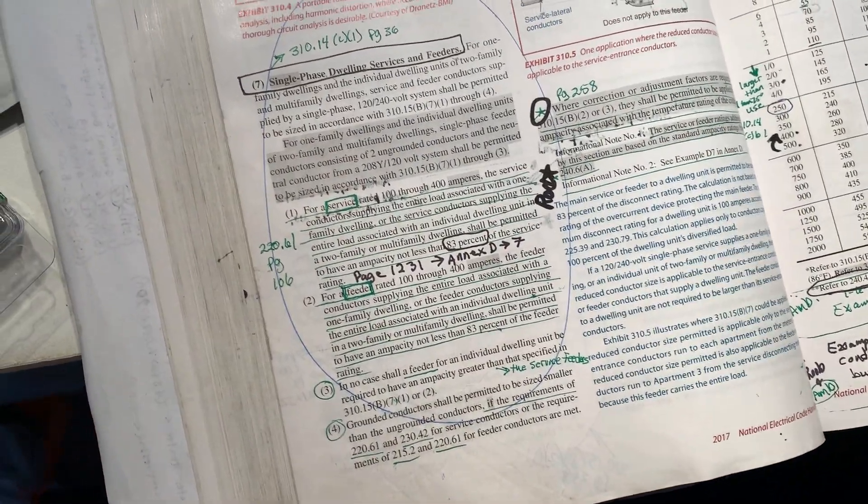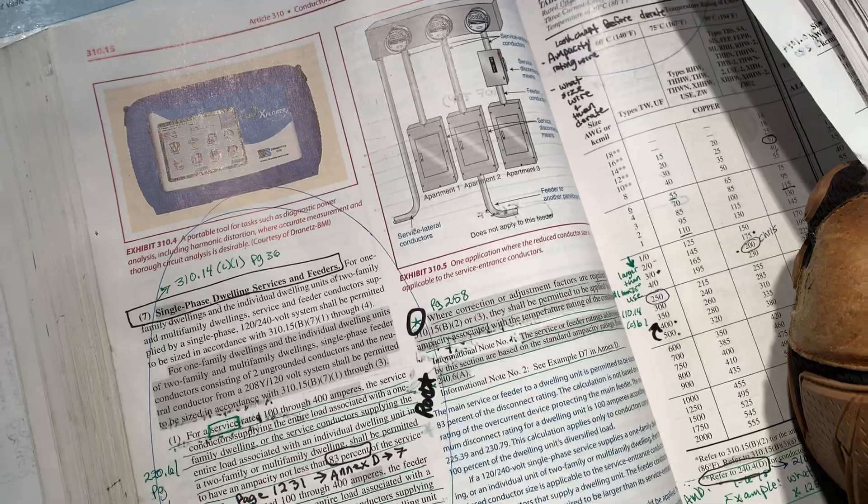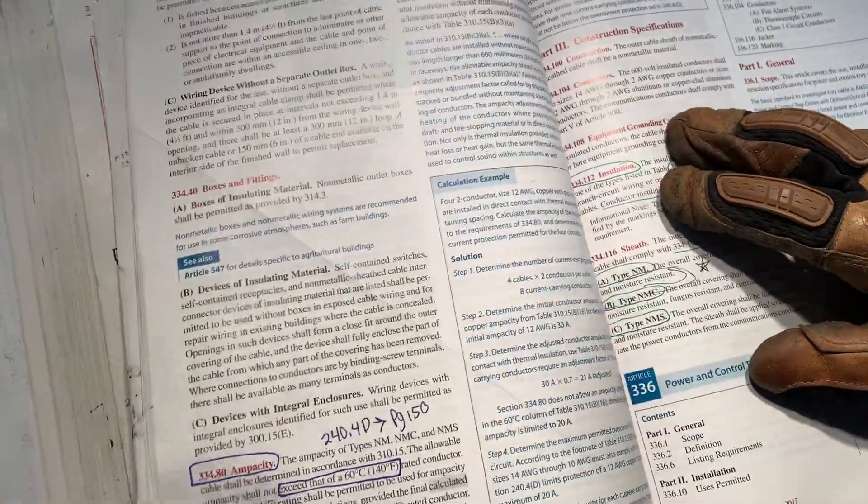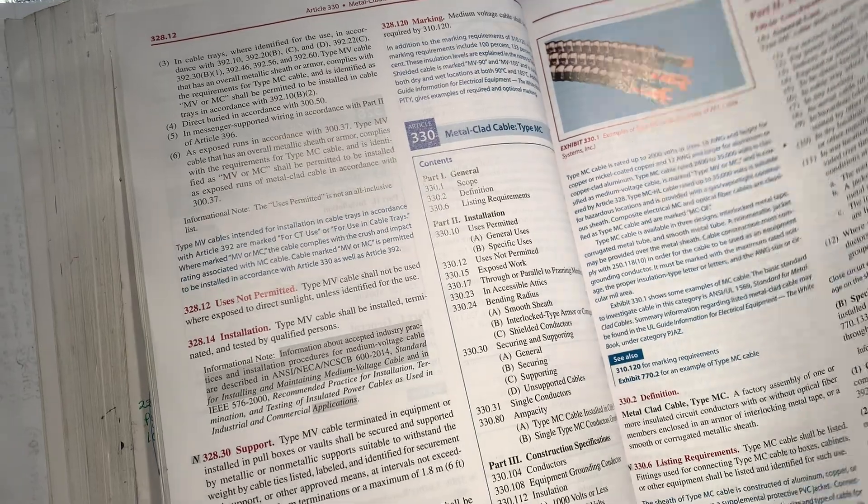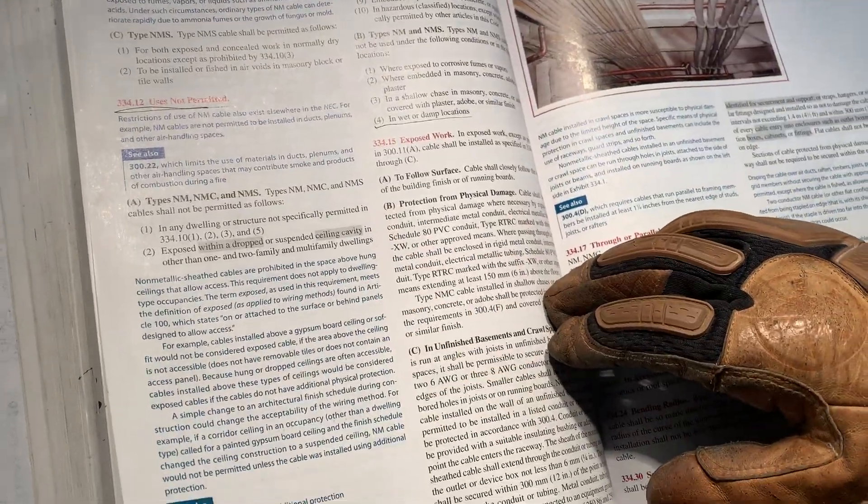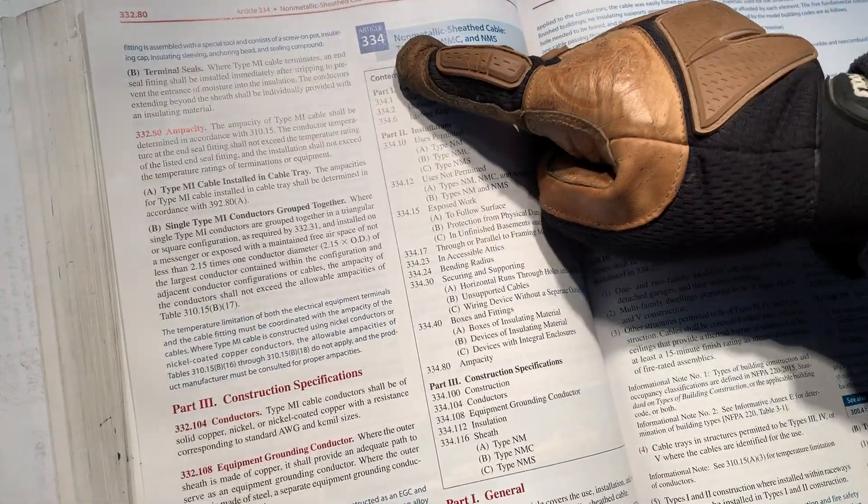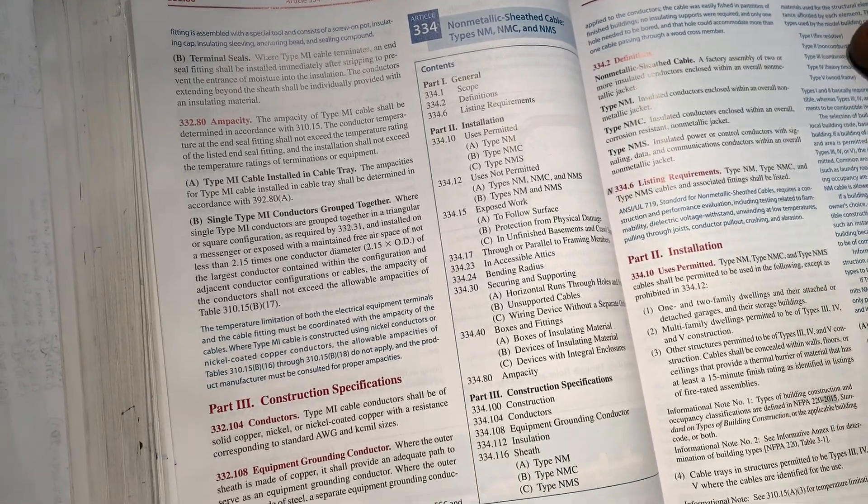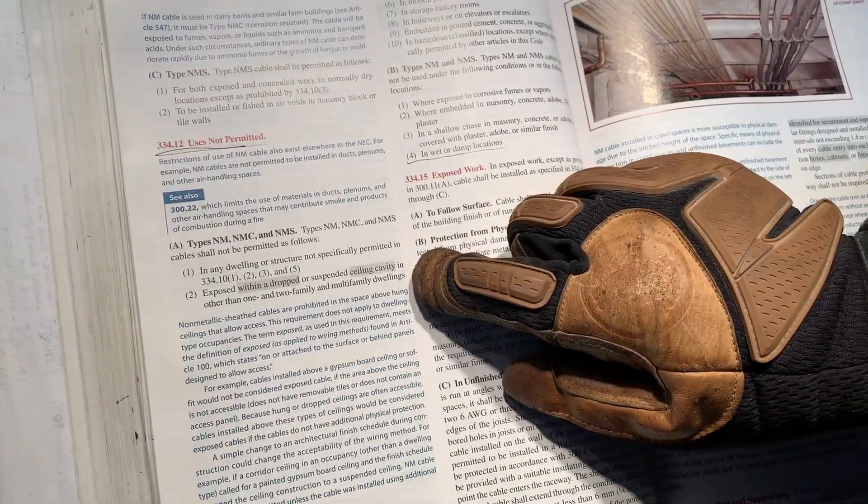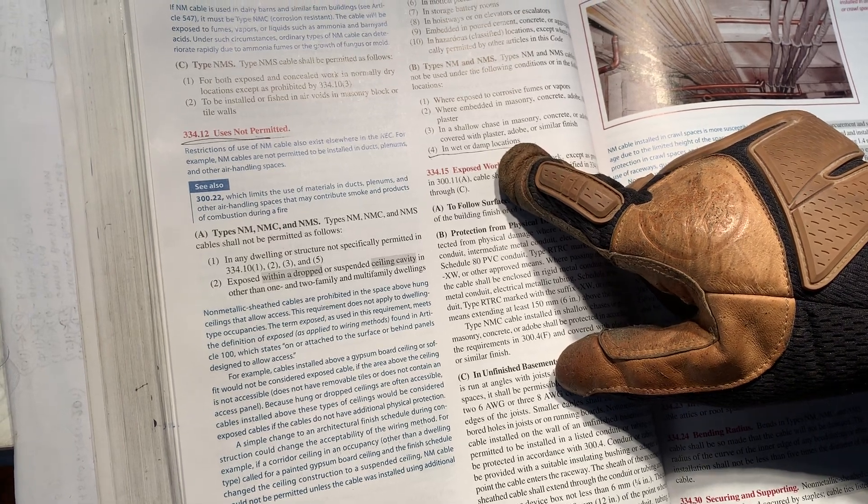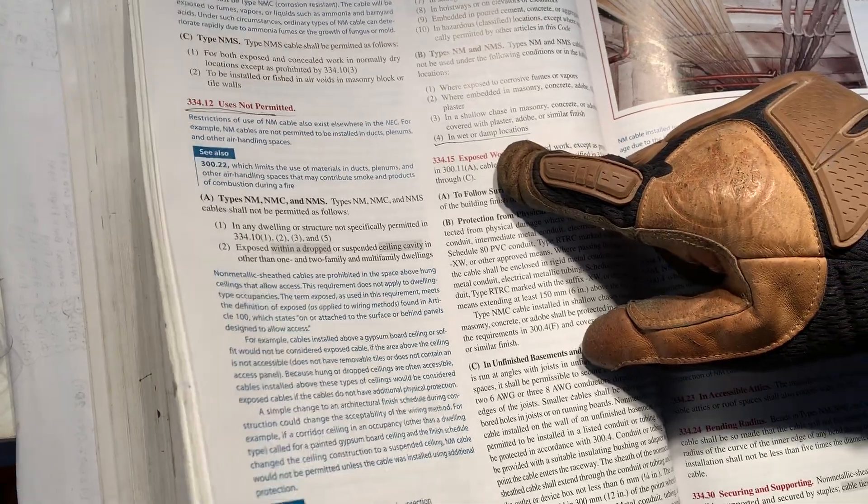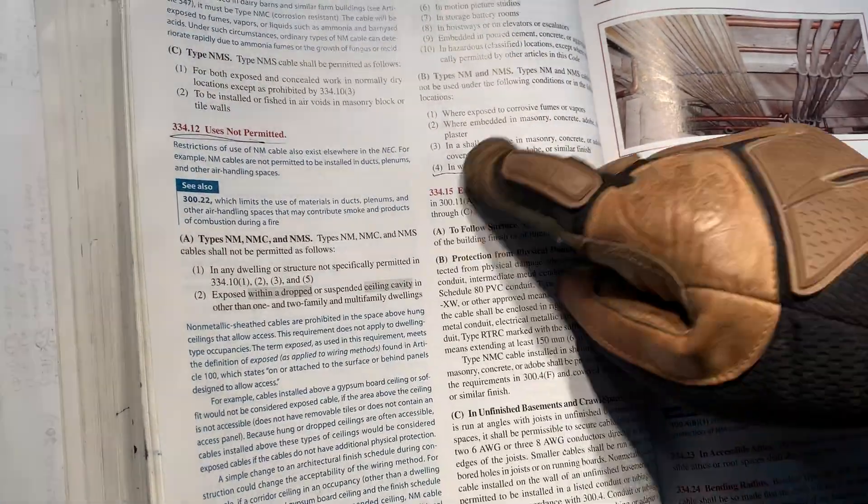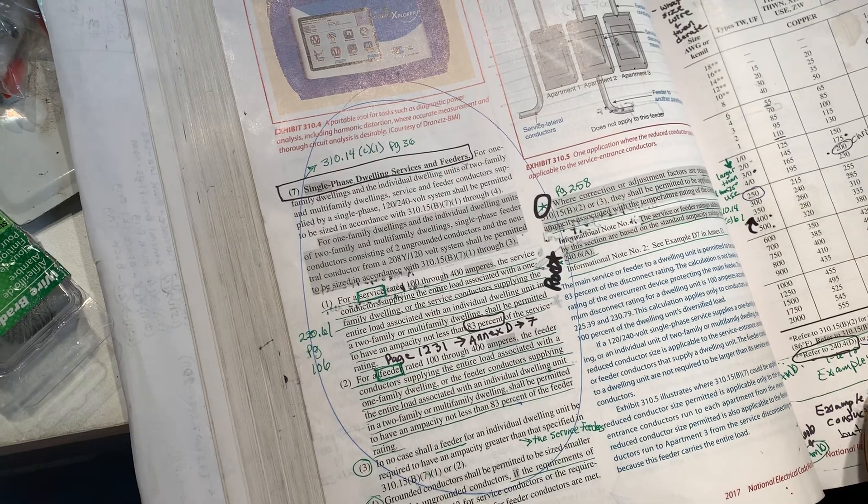But then the other thing we had to pay attention to is make sure, if you guys are thinking of running this, you're not allowed to take NM cable, article 334, I believe. Let me see if I'm right. 334. I was right. You cannot, for use is permitted, it talks about, but use is not permitted. You are not allowed to go outside with this wire anymore. It is not allowed to be in a damp and a wet location. 334.12b4. I call it BS because some of this gets a little bit too much. But the point of the matter is, right here, you cannot put this in a conduit anymore. And nor are you going to get that in unless you put in a 1 inch.